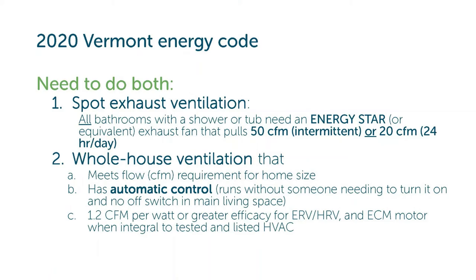Vermont requires new homes and homes undergoing retrofits, such as a bathroom remodel or other space renovation, to have: Number 1. Spot exhaust ventilation in the bathrooms with a shower or tub, pulling 50 cubic feet of air per minute using a manual on-off switch, or a 20 CFM always on. The bath fans must be ENERGY STAR certified or equivalent in performance.